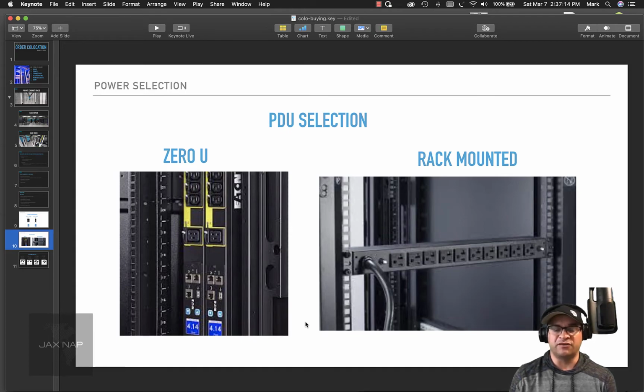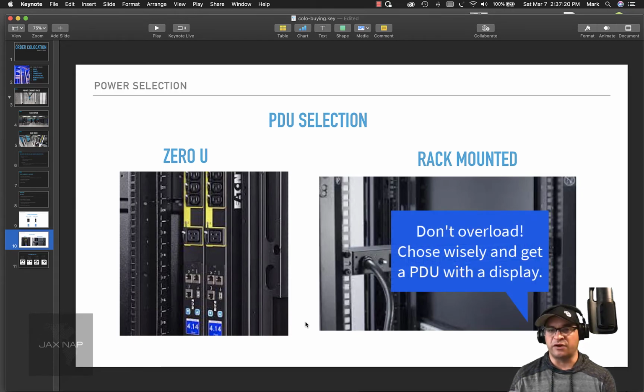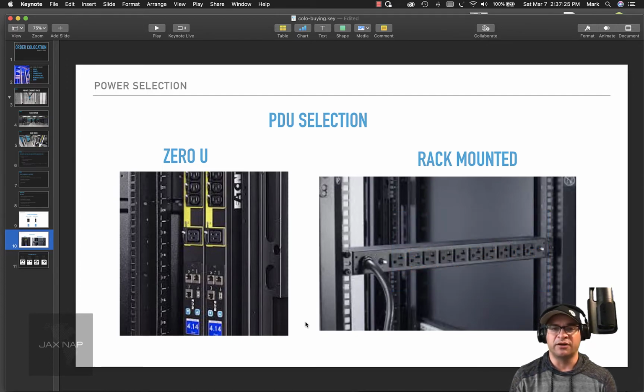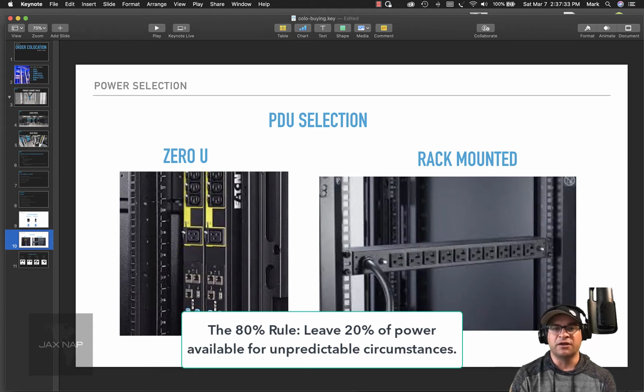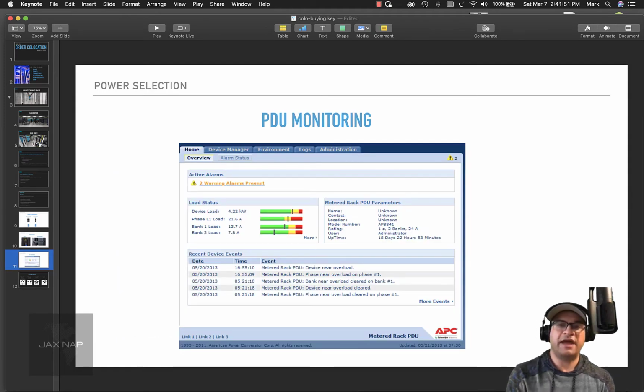So if I put in too many servers inside my rack and I have a 120 volt 20 amp circuit and I start to put in 20 servers that all eat 1 amp each, I'm going to end up popping my breaker. You also have to understand that a lot of the time data centers use what's required, called an 80% rule. That means if you have a 20 amp circuit, you're only allowed and required to use 16 amps of it. You have to keep a threshold between 80 and 100% in case there are fans that spin up, and you want to keep a little buffer zone below the 20 amps so you don't pop your breaker.